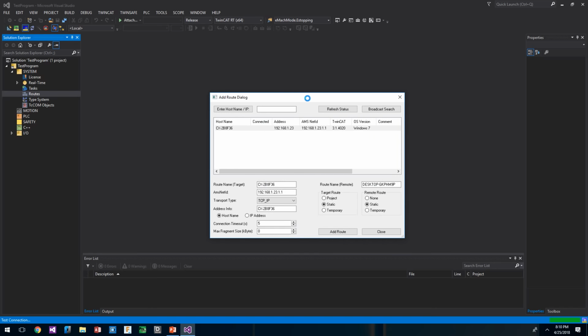That's kind of nice because you can push your PLC a little bit harder. Rather than trying to stay below 50%, you can maybe go a little bit higher to 60 or 70% even. It's getting kind of risky when you get that high, but that's one thing that you can do to push things a little bit. I'm just going to leave it as is for now. This should work just fine for what we're doing. We shouldn't really need to mess with it.